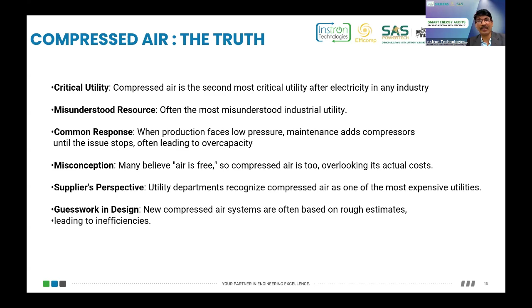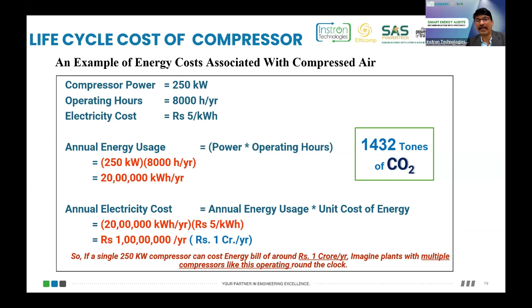The main reason for people not focusing on compressed air is that they actually do not know the operating cost of the system. Here is an example: a simple 250 kilowatt compressor running at an industry or a simple plant. You can take a value of 5 rupees per kWh per unit. The running cost itself comes to around 1 crore. Generally, I have seen plants with more than 10 megawatt of connected load for compressed air systems. A single 250 kilowatt compressor can generate the equivalent of 1432 tons of CO2. So you can imagine the value of carbon added to the atmosphere because of compressor operation. We should know the operating cost and then manage it accordingly.